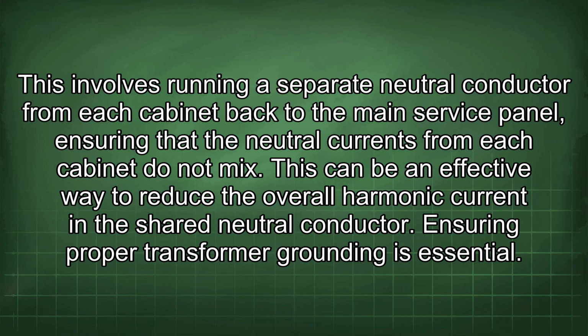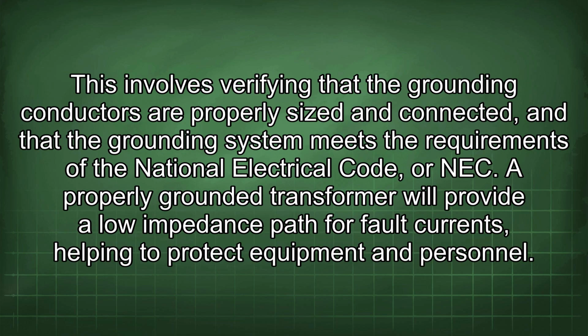Ensuring proper transformer grounding is essential. This involves verifying that the grounding conductors are properly sized and connected, and that the grounding system meets the requirements of the National Electrical Code, or NEC. A properly grounded transformer will provide a low impedance path for fault currents, helping to protect equipment and personnel.